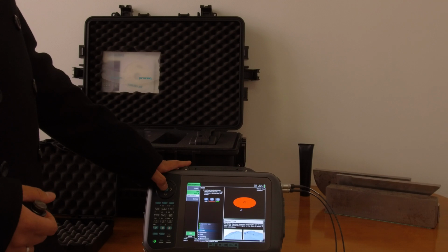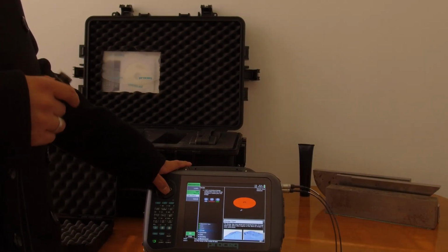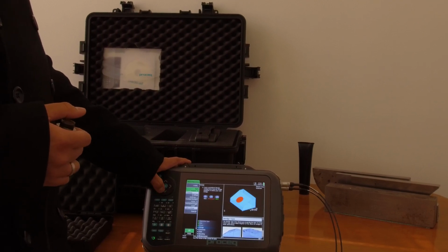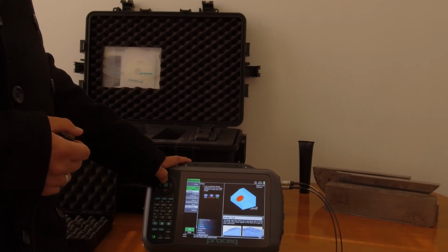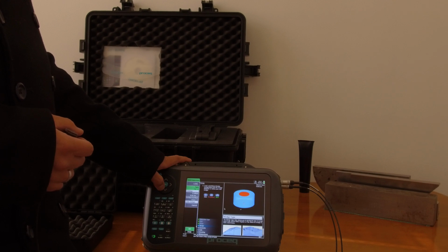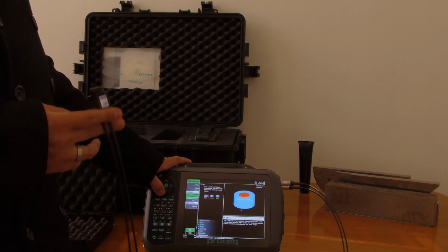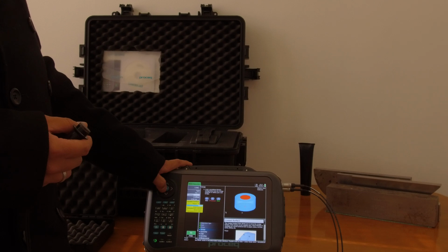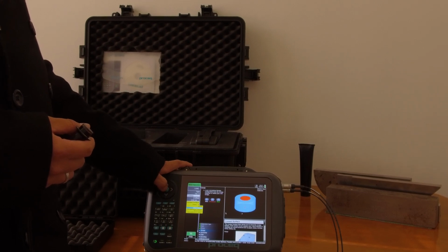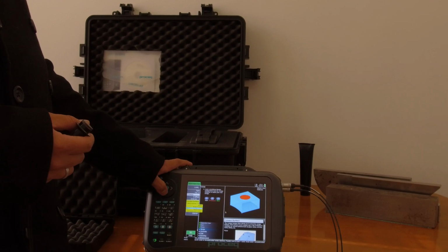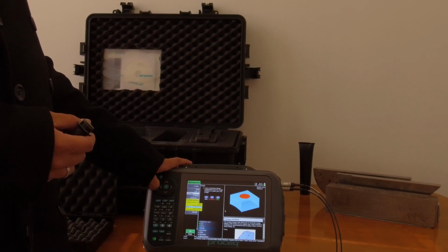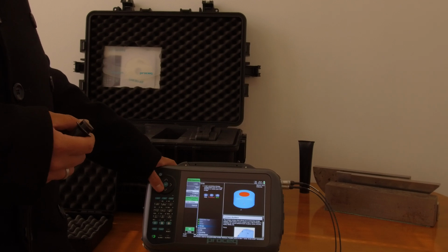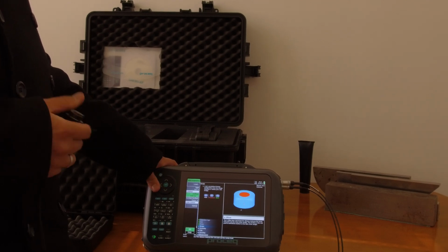Okay, this one here would be if we wanted to nominate a wedge. So we could say that we have a wedge. You could say you have an angular wedge, and you could nominate the parameters for that, or you could say it's flat and nominate the parameters for that one. You can then offset the X for that one, and you can say whether the contact surface is planar, concave, convex, or circumferential concave or circumferential convex. Okay, I think in this instance let's just leave it at 10 and planar.